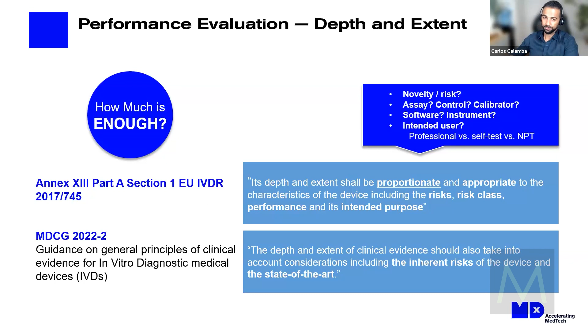So in clinical performance, really clinical performance is defined in the regulation as the ability of an IVD to yield results that correlate with a particular clinical condition or a physiological process or state in accordance with the target population and intended use. And that's why for clinical performance, there's a clear link between what you're going to be demonstrating against the intended use that you've defined for your device.